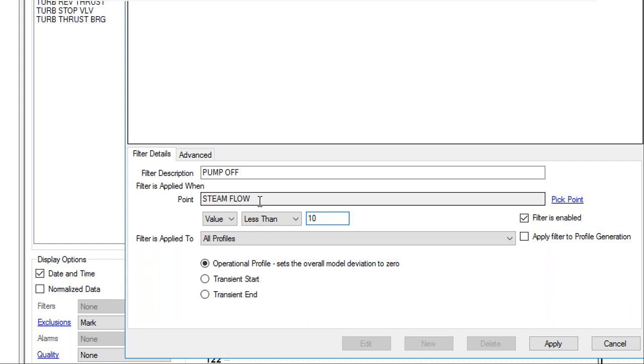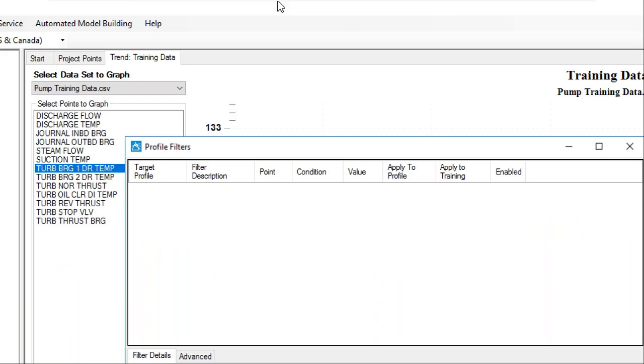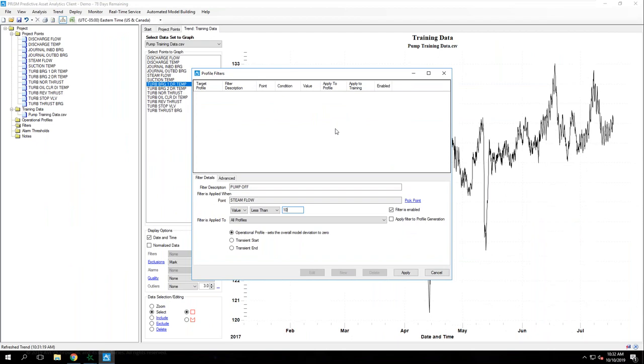What we can do with filters is create logical conditions. In this case, a filter where our pump is turned off. I've selected a steam flow tag, and my logical condition is whenever the steam flow is less than 10 kBh. Under those conditions, we'll turn off the operating profile, basically keeping the model from running, so you won't generate any nuisance alarms or warnings when that occurs.